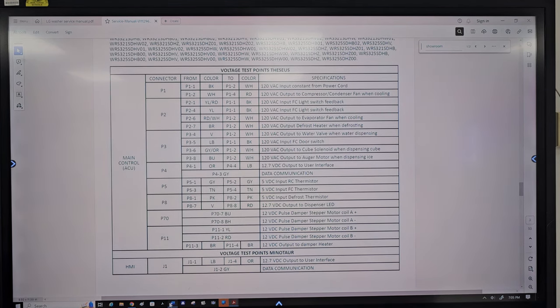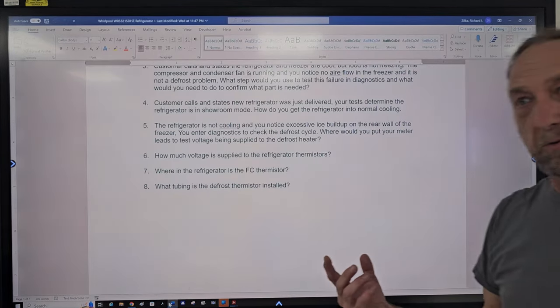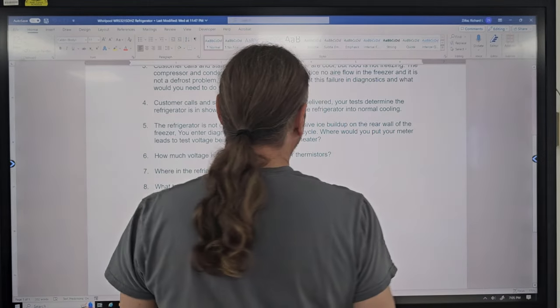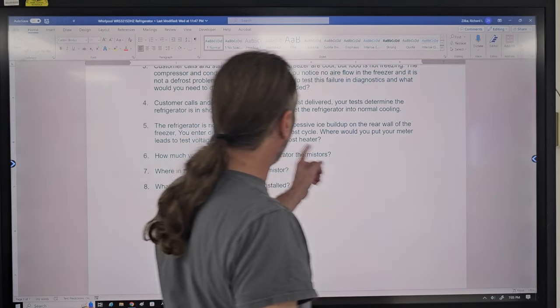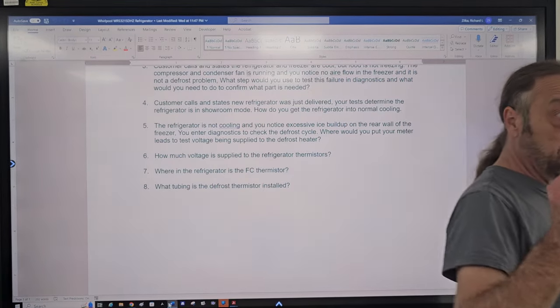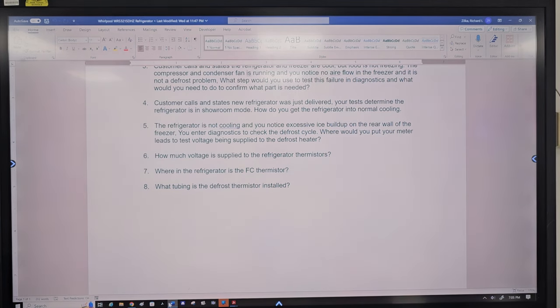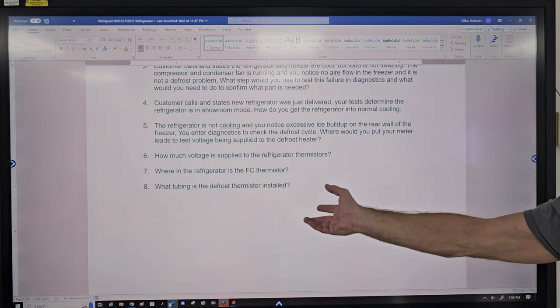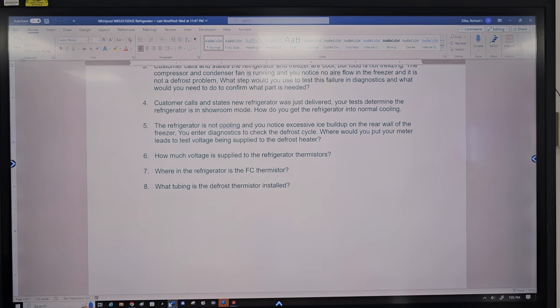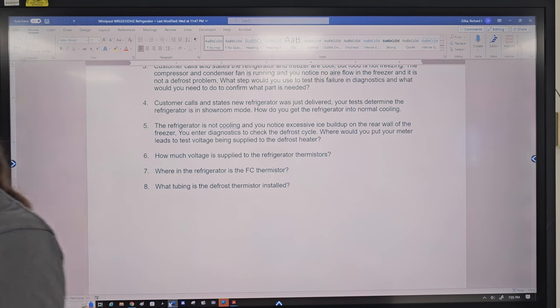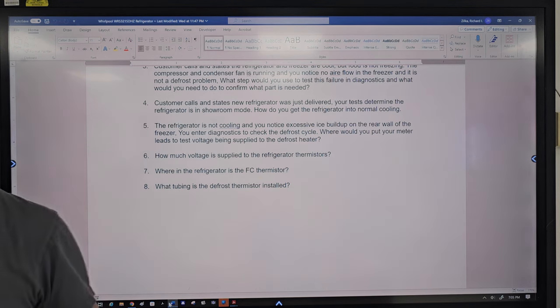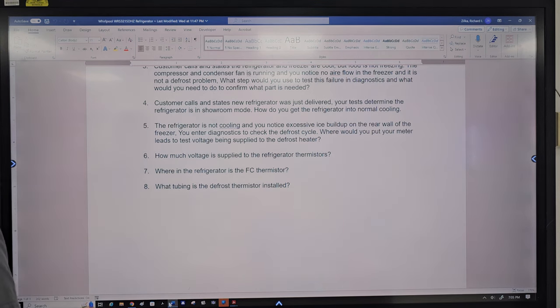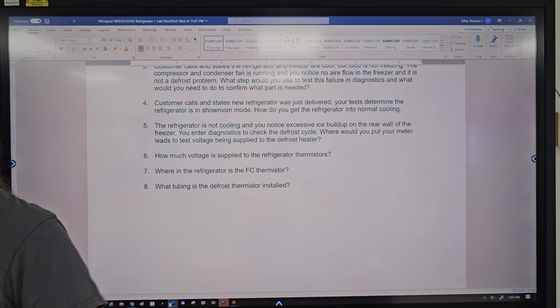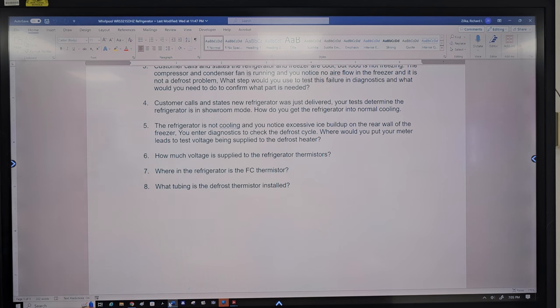It had the two thermal fuses, I pointed them out to you. So where would you put your meter leads to test voltage supply to here? You put it on the board on those two pins I told you, and we'd look for 120 volts when we're in that step. If we have 120, we know the board's sending power out. We need to then check to see if the thermal fuses are bad or the heater's bad. But if we've got voltage, we know we've got to go down to those components to check them.